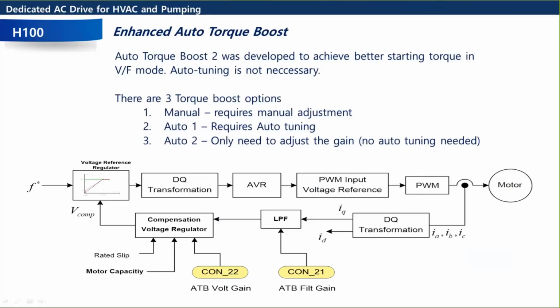So manual torque boost is just a percentage. I think it defaults to 2 or 3%. So it's going to boost up your voltage 2 or 3%. It's not dynamic at all. Then there's Auto Torque Boost 1, which is the second one we're listing here. That one, it works okay, but you got to do an auto tune.